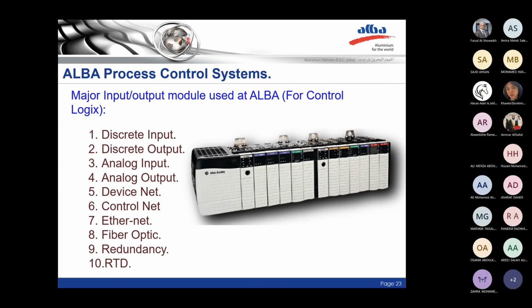And we have ControlNet, which has more or less become obsolete, but still in some places it is in use. Even ALBA, I think, has it. Ethernet is widely used and still in use. Then fiber optic, where once you splice the fiber optic cable, you can hook it directly to the card, which is located in the same chassis. And then we have the redundancy card. The purpose of the redundancy card is to synchronize between two controllers, like the one we saw previously, where we have two ControlLogix chassis. To assure the synchronization of all the information between two controllers, the redundancy card is in use.